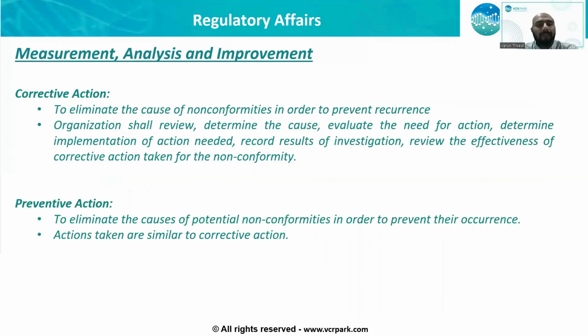Finally, we talk about corrective and preventive action. Please keep in mind, corrective action is to eliminate the cause of non-conformity in order to prevent its recurrence. And preventive action is to eliminate the causes of potential non-conformity. Corrective and preventive action never exist together, because for a corrective action to exist, the issue should have happened. We do preventive actions where we preempt an issue that can happen, and then we put necessary mitigations around it.